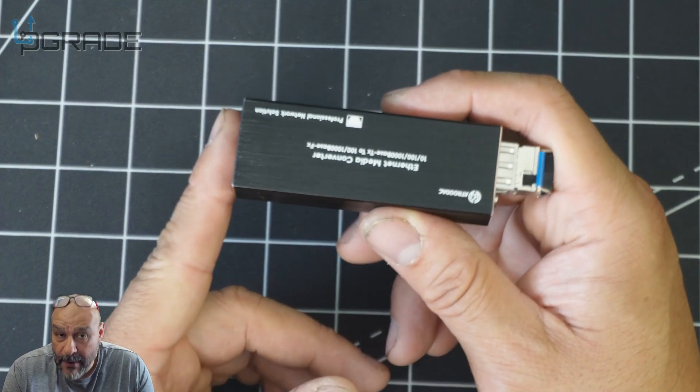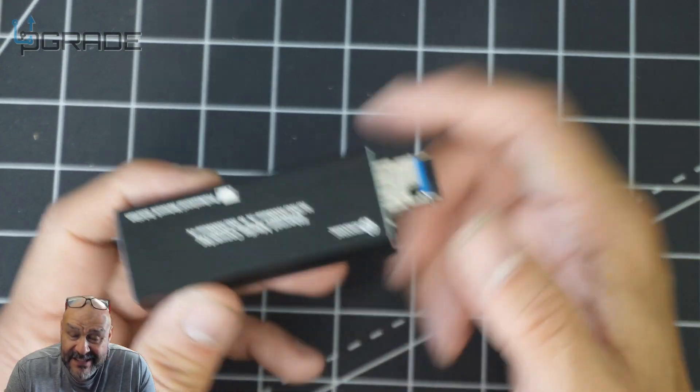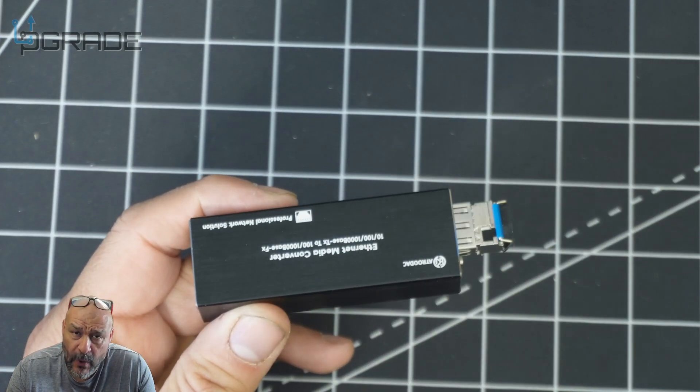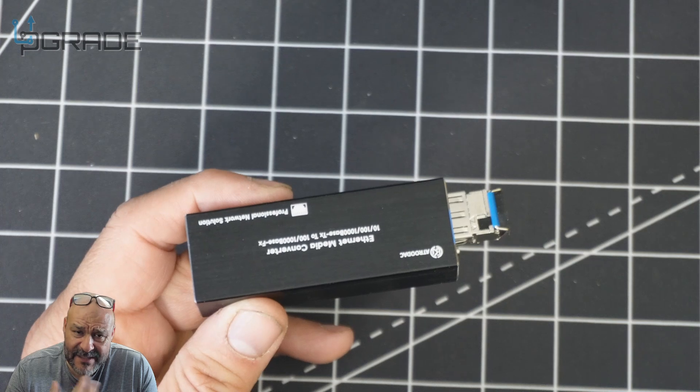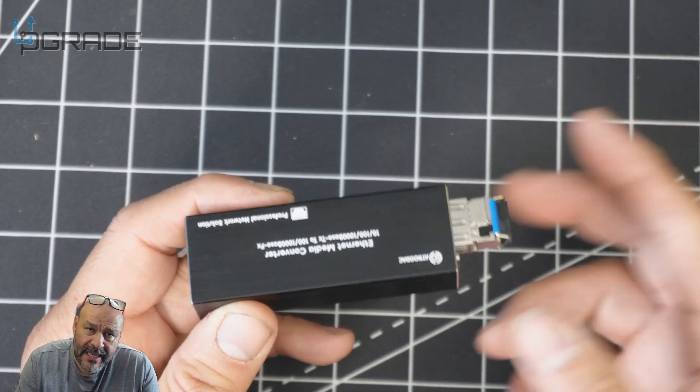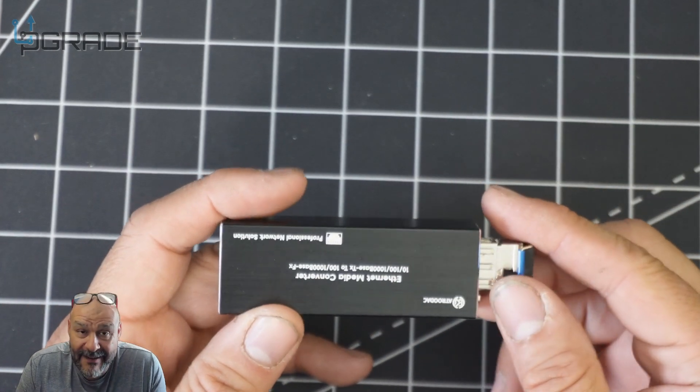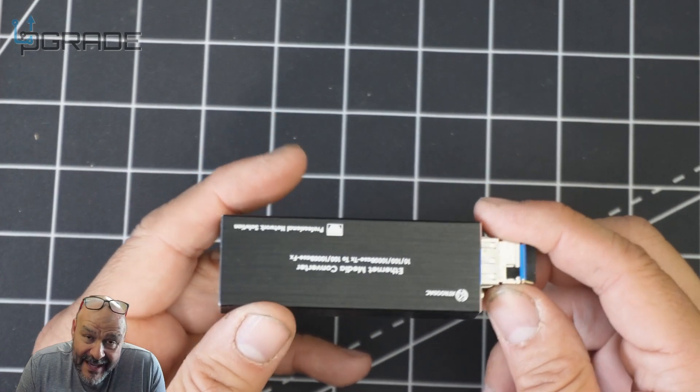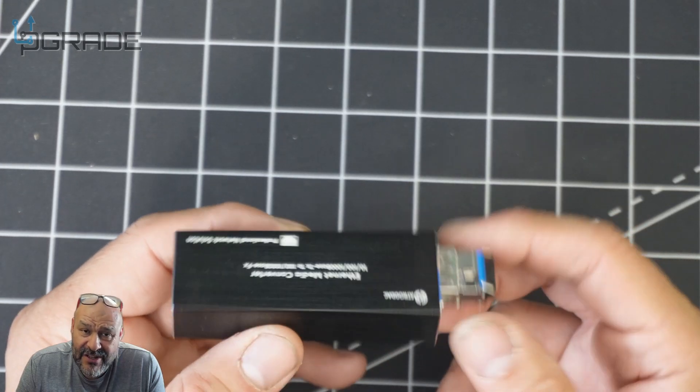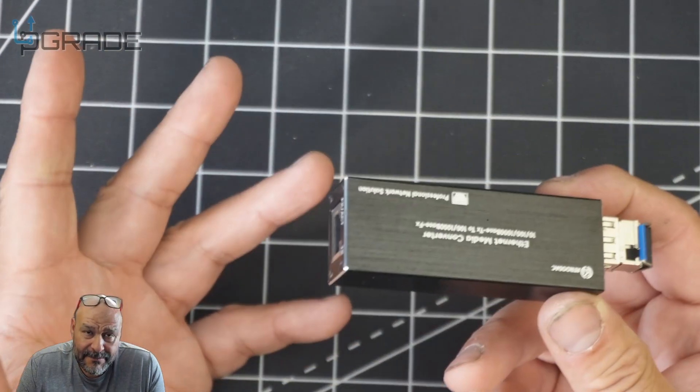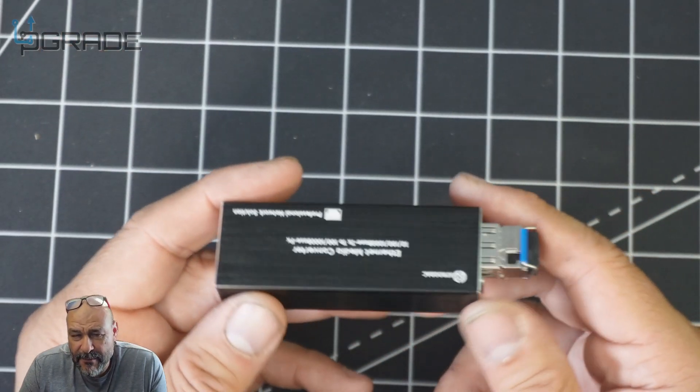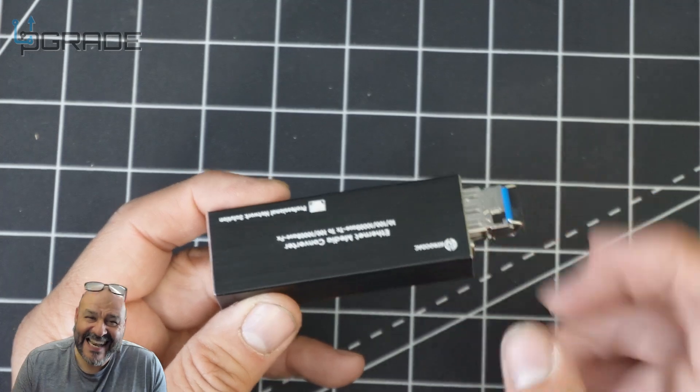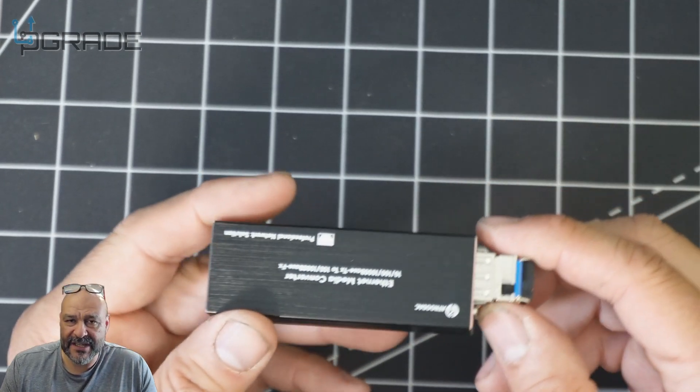So that's the only thing. If you're going to do outdoor, you would need an outdoor graded fiber because this deteriorates quickly within a week if it's exposed to the sun too much. The exposure of the sun will make it very fragile and you'll start losing connectivity or even probably won't connect.